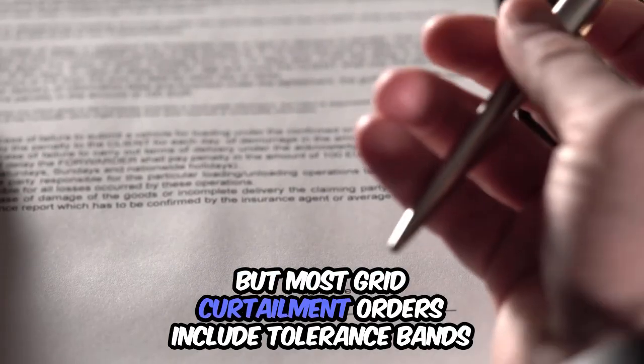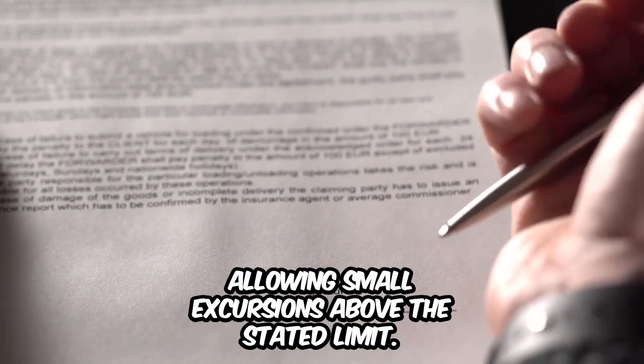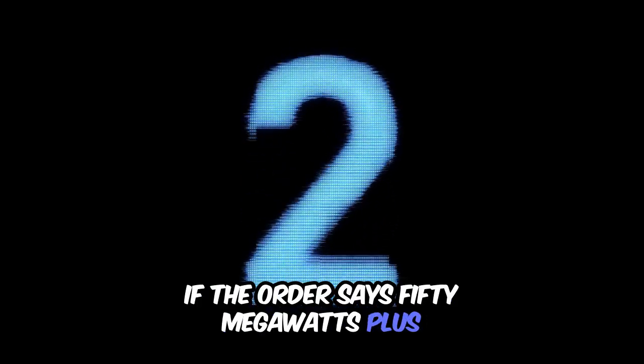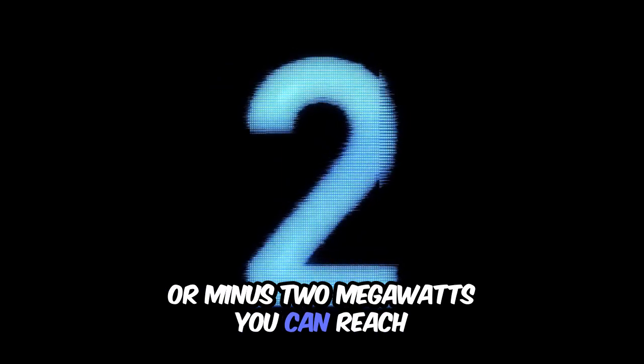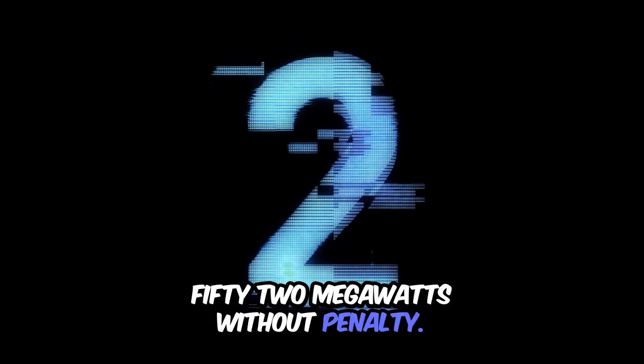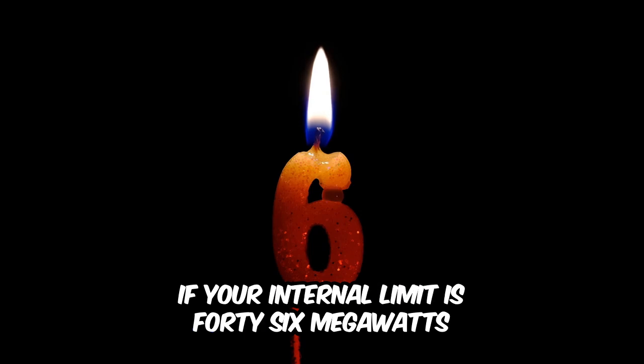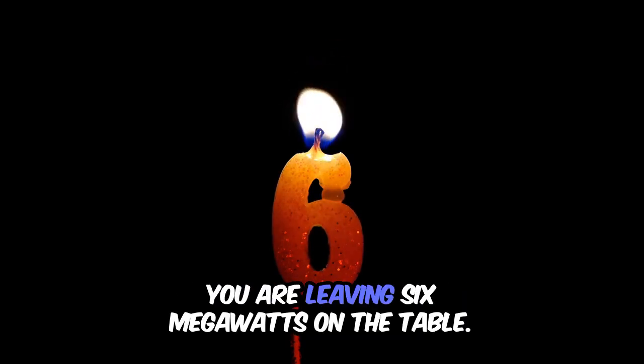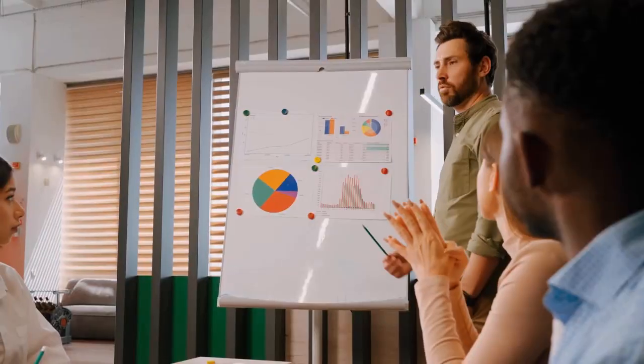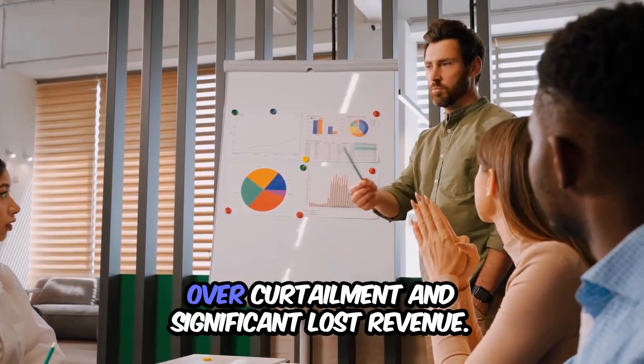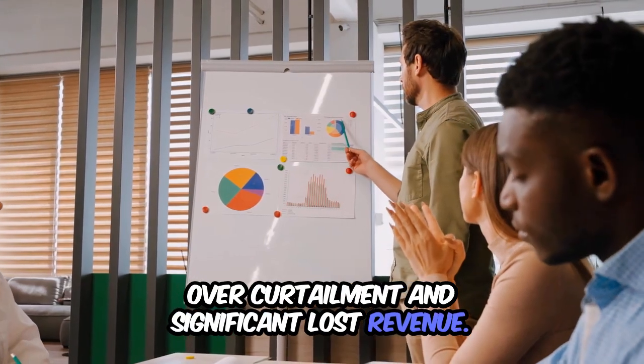But most grid curtailment orders include tolerance bands allowing small excursions above the stated limit. If the order says 50 megawatts plus or minus 2 megawatts, you can reach 52 megawatts without penalty. If your internal limit is 46 megawatts, you are leaving 6 megawatts on the table. That gap can equal 12% over curtailment and significant lost revenue.